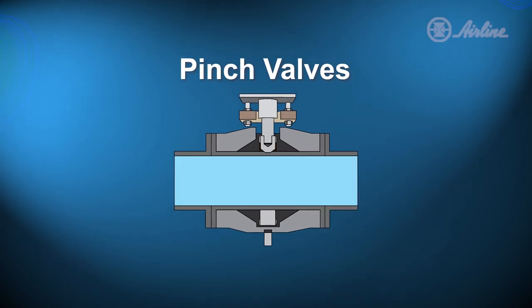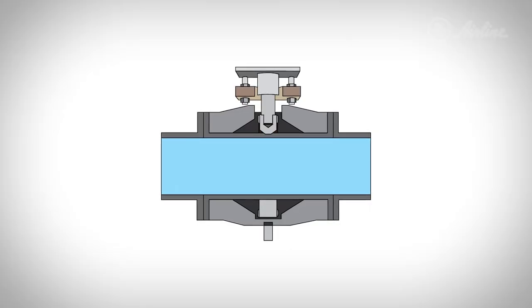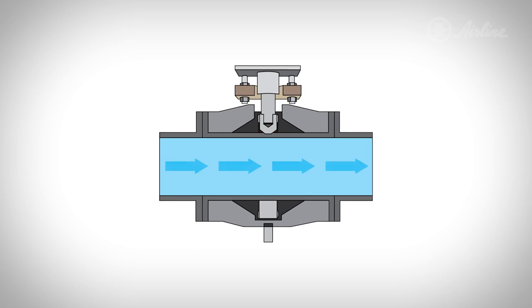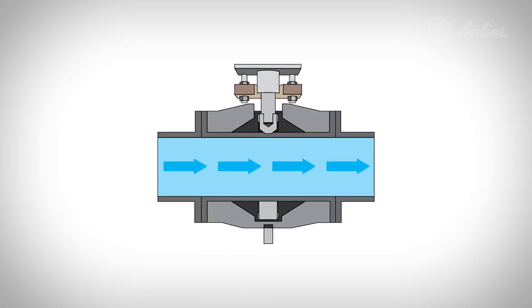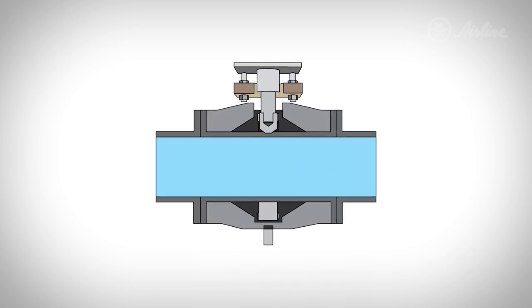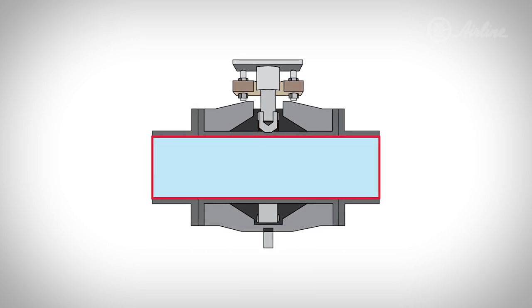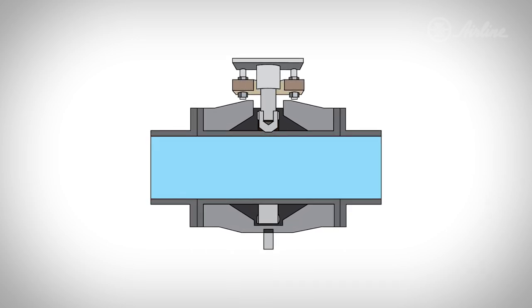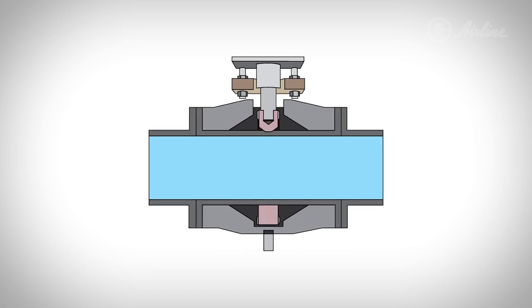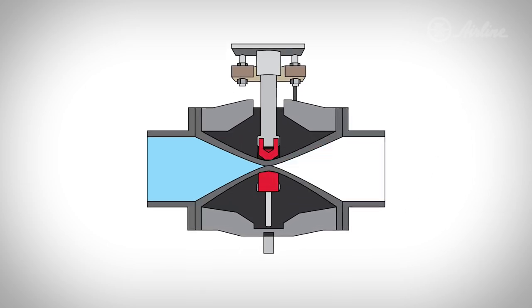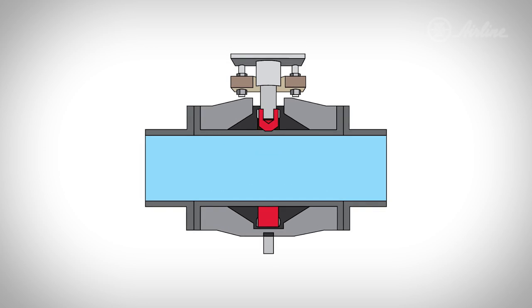The last valve we'll be discussing are pinch valves. Pinch valves are named after the pinching mechanism that isolates the medium flow path. In this illustration we have a pinch valve along with the flow path of the medium. Pinch valves require flexible tubing to carry the medium, and unlike other isolation valves, this is the only wetted part of the valve. When the pinch valve is activated, the pinch bar squeezes or pinches the tube and isolates the flow path.